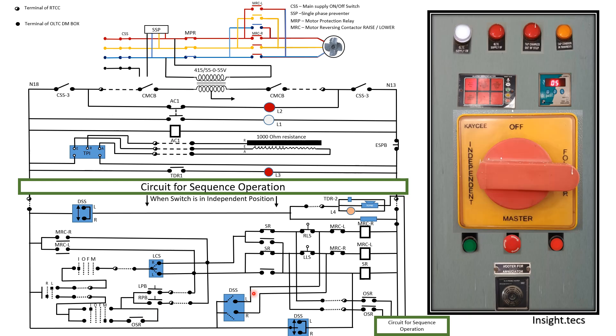On the RTCC panel we have an independent, follower, and master switch. When remote is selected and independent is selected, the operation of this transformer itself for tap changing will be done independently. When master is selected, after the operation of this transformer, the other transformers' steps will also be changed subsequently. If follower is selected, whenever the master transformer's tap changing is done, this follower transformer will also automatically change its step position.